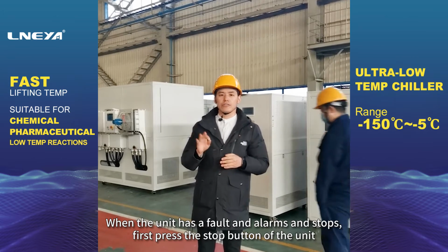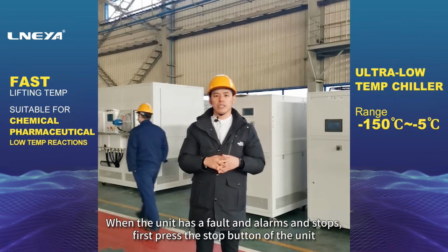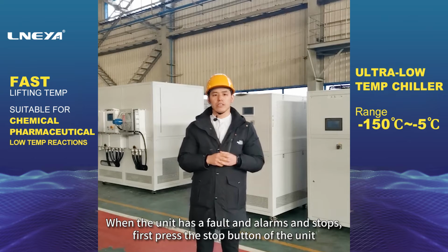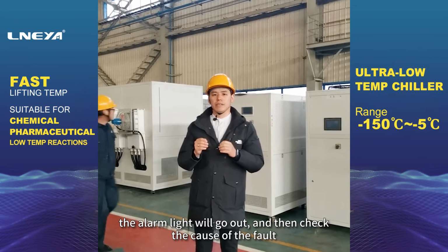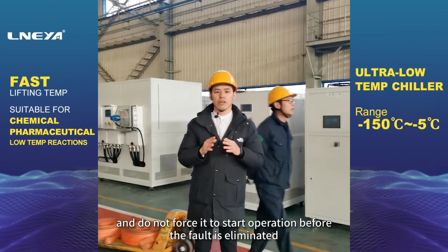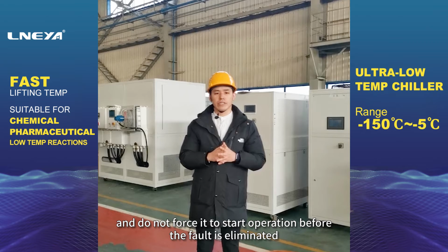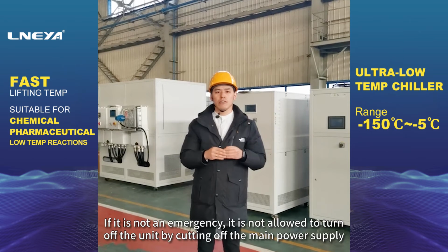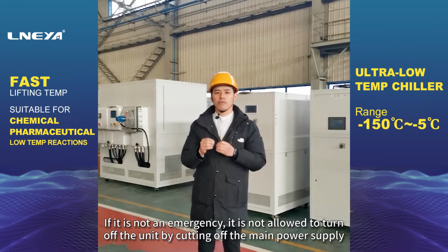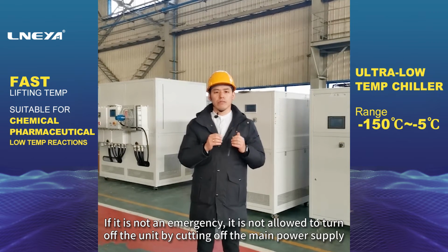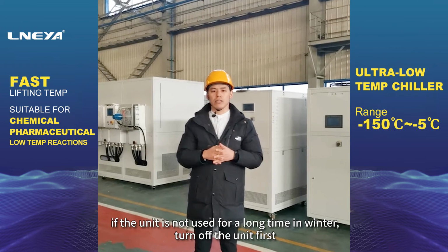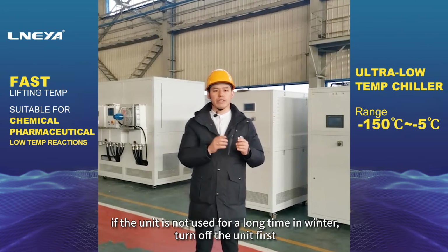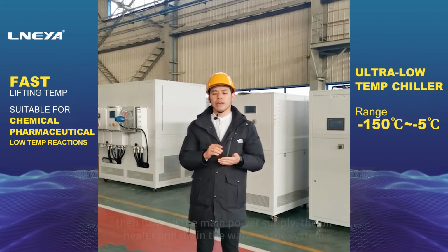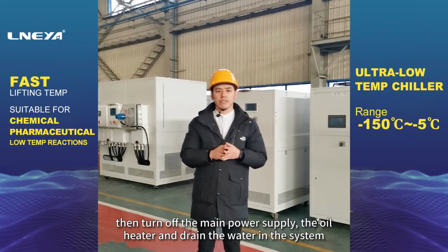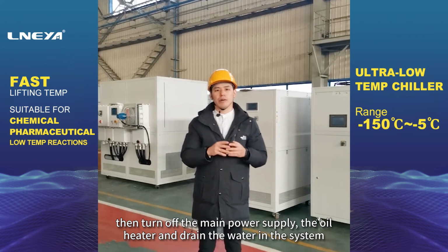Third, when the unit has a fault and alarms and stops, first press the stop button of the unit, the alarm light will go out, and then check the cause of the fault, and do not force it to start operation before the fault is eliminated. Fourth, if it is not an emergency, it is not allowed to turn off the unit by cutting off the main power supply. If the unit is not used for a long time in winter, turn off the unit first, then turn off the main power supply, the oil heater, and drain the water in the system.